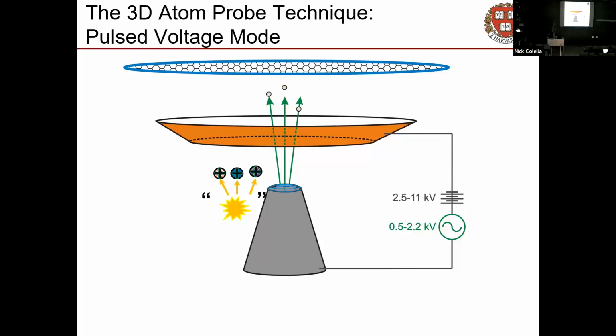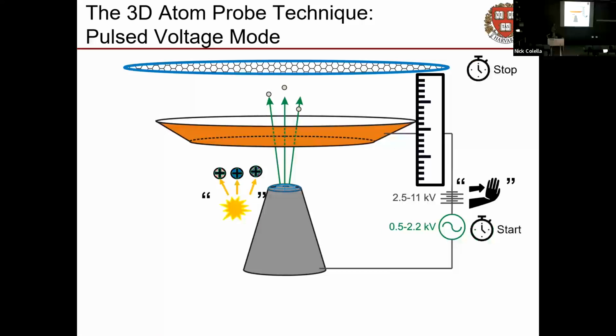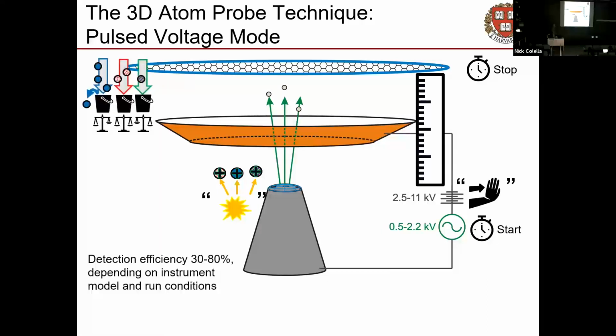They come off as ions, they get accelerated away, they go up through the electrode and hit our detector. We know the distance between the two. We know the amount of voltage we applied, which means we know the energy. We have our stopwatch, so we know the time. Fabulous. We got time of flight mass spec, and our detector is a position sensitive detector. So depending on where they land, we can trace them back by simulating their trajectories and work out where they started, and that gives us their spatial resolution. Cool. And then we just sit there and accumulate atoms.